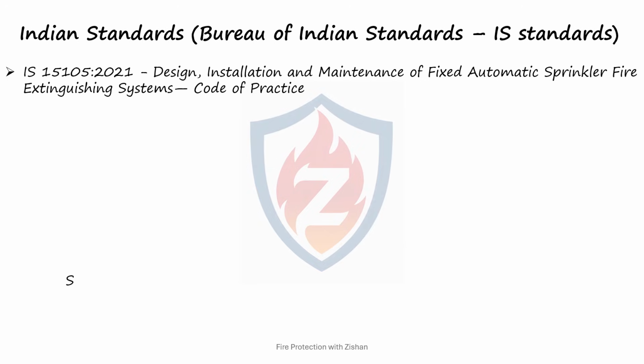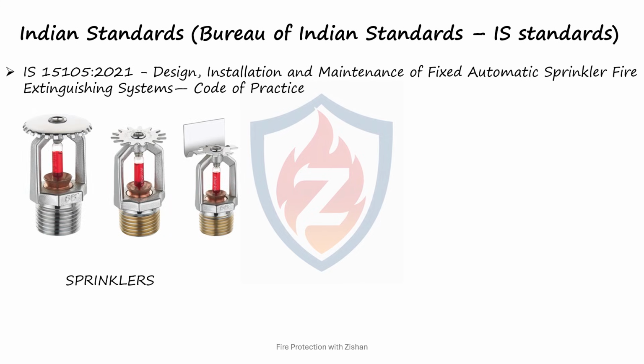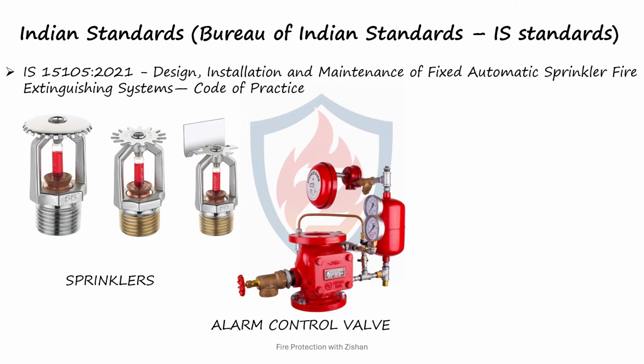On the left, we can see various types of sprinkler heads. These are heat-sensitive devices designed to operate automatically when the surrounding temperature reaches a predetermined level. An important feature of sprinkler systems is that only the sprinkler closest to the fire activates, allowing water to be discharged directly onto the affected area. In the center is the alarm control valve, one of the most critical components of the sprinkler system. It controls the water supply to the sprinkler network and initiates alarm signals whenever a sprinkler operates, providing immediate notification of a fire incident.